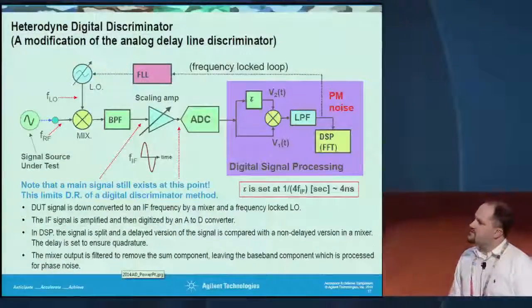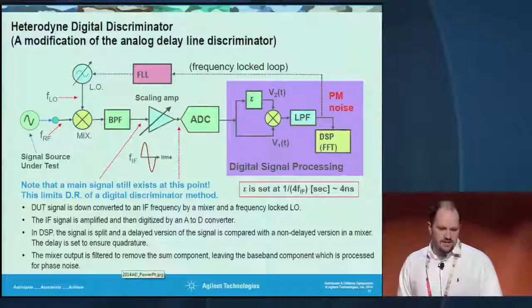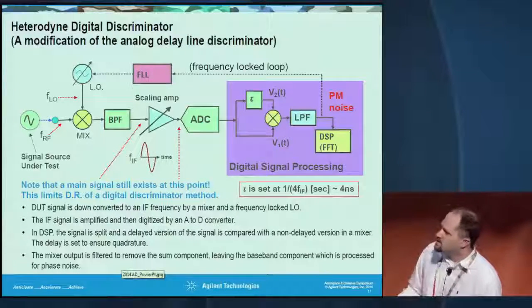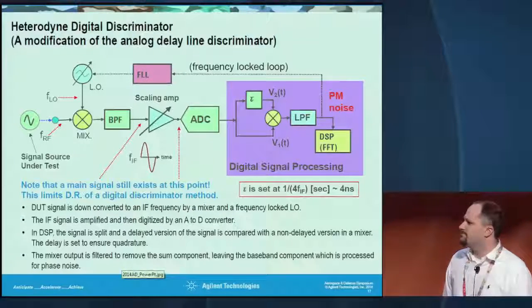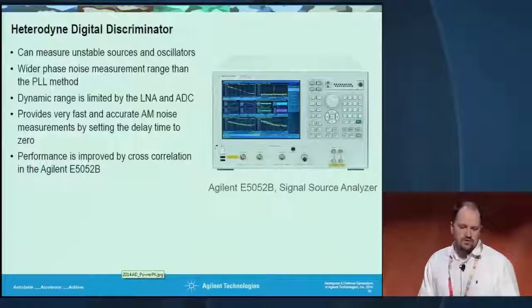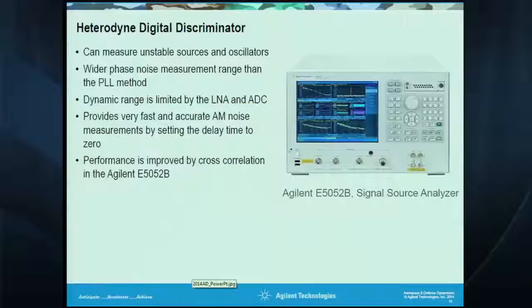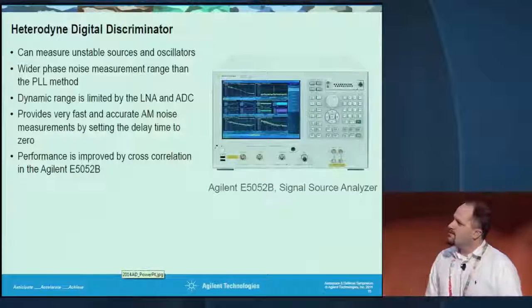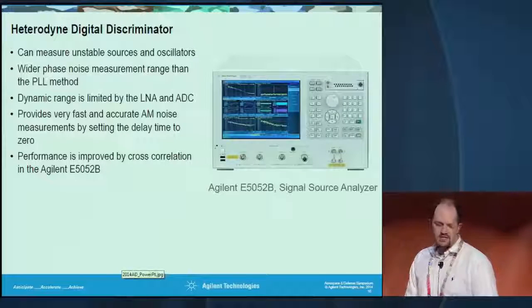We actually use the heterodyne digital discriminator in our E5052B, which is a signal source analyzer. Basically, the DUT is down-converted by a mixer — we do this up to 26 GHz. The IF signal is amplified, then we use an A-to-D converter and digital signal processing to split the signal and do the comparison in the digital domain. You can measure unstable sources and oscillators, including voltage-controlled oscillators that move versus time. The dynamic range is limited by the low noise amplifier and ADC performance of the signal source analyzer. It's pretty fast and accurate, and improved by cross-correlation, which we'll talk about next.